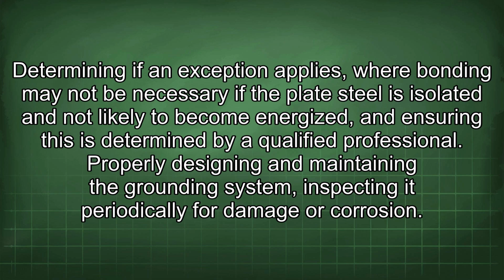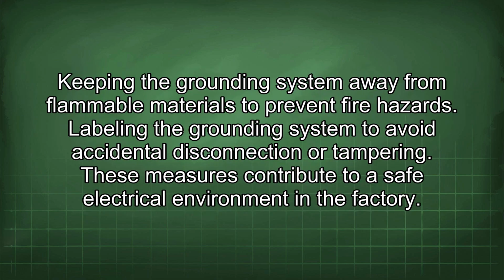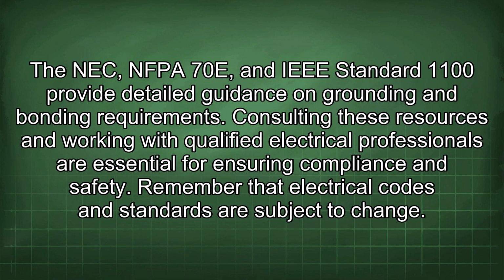Properly designing and maintaining the grounding system, inspecting it periodically for damage or corrosion. Keeping the grounding system away from flammable materials to prevent fire hazards. Labeling the grounding system to avoid accidental disconnection or tampering. These measures contribute to a safe electrical environment in the factory. The NEC, NFPA 70E, and IEEE Standard 1100 provide detailed guidance on grounding and bonding requirements. Consulting these resources and working with qualified electrical professionals are essential for ensuring compliance and safety.